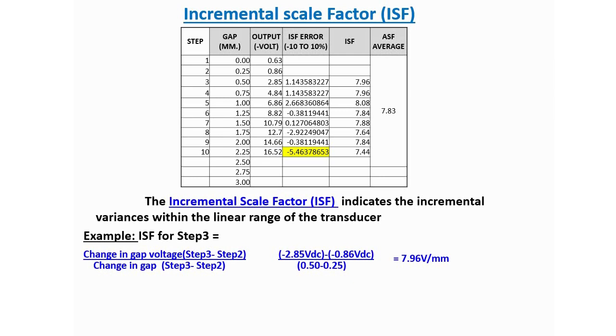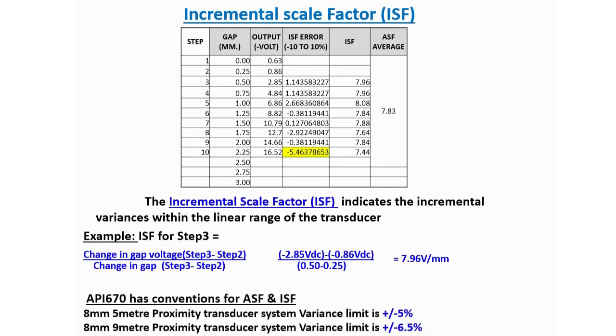The steps to verify the scale factor and how this chart is derived will be explained further in this video. As per American Petroleum Institute Standard 670, these are the variance limits specified for ASF and ISF.